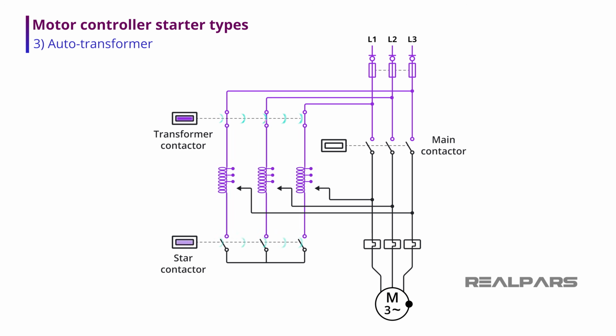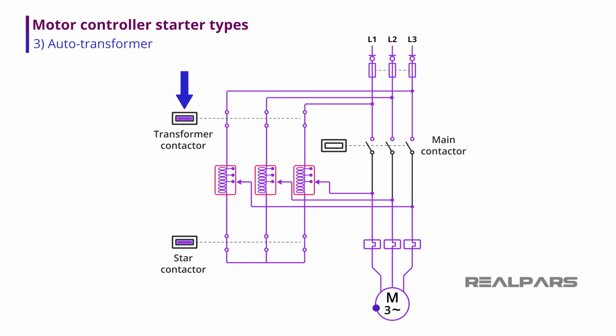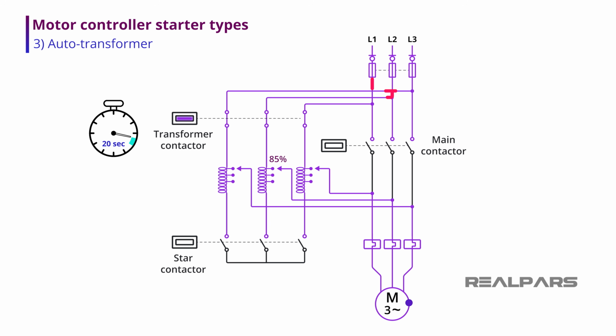When the motor starts, two contactors pull in. One of these contactors energizes a transformer circuit, and the other forces the transformer into a star configuration. The tapped output from the transformer is connected to the motor leads at the start. Once the motor reaches 85 to 90% of full voltage, the star contactor opens, and the transformer then acts as a choke to limit the voltage and the current to the motor. The main contactor then closes, and the motor controller acts as an FVNR with full voltage to the motor.